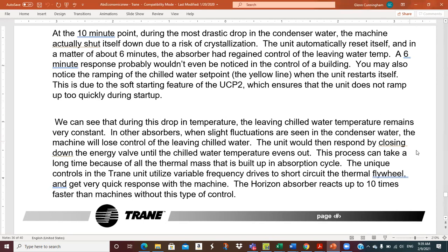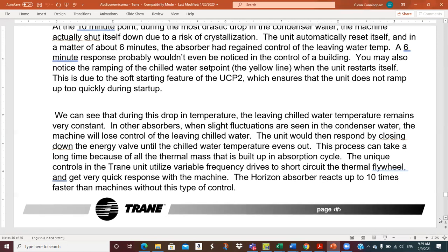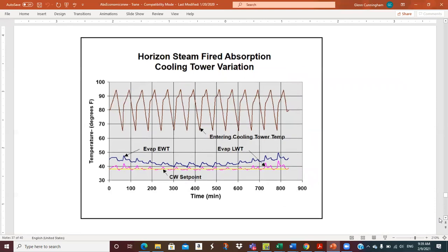So where the other guys are, these slides have been out there a number of years, so I expect all the manufacturers probably have this stuff these days. Okay, so here's another fairly extreme one. So this is simulating poor cooling tower temperature control. And so you see the seesaw pattern. This is what's really being changed. And then we're going to look at the response of the chiller to it. So we're going to ramp from 95-degree water down to 65-degree water. And I don't know, what is that, a 20-minute cycle or something? Probably says down here.